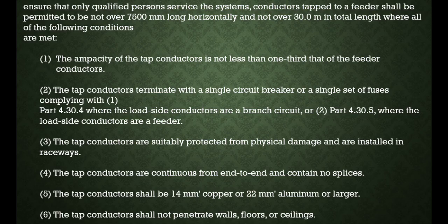To ensure qualified personnel service the systems, conductors tapped to a feeder can be up to 7,500 mm horizontally and 30 meters in total length if tap ampacity is at least 1/3 of the feeder. Tap conductors terminate with a circuit breaker or fuses complying with the ampacity requirement.